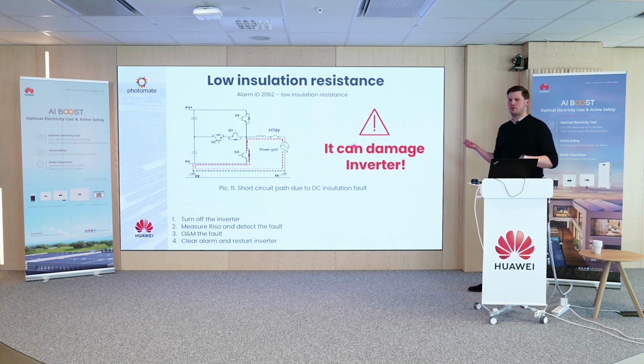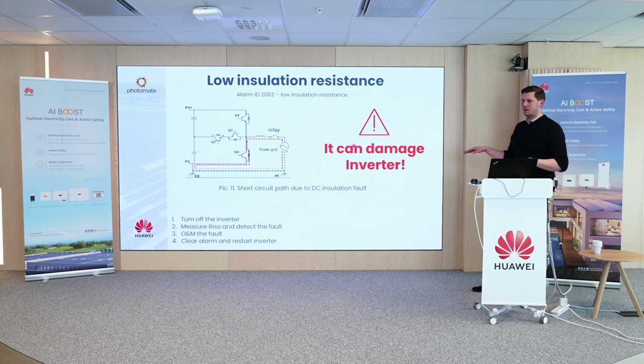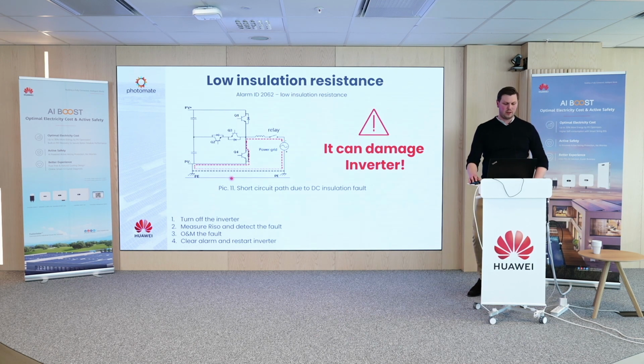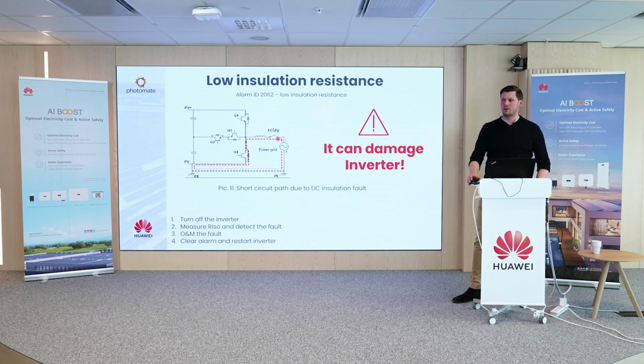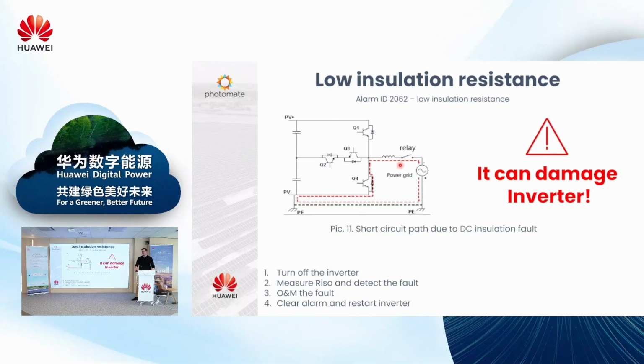But if you have a problem with an alarm like this, you should turn off the inverter before you go on site, or ask the owner to do it for you. Because the inverter, which will be trying to check this insulation resistance, will have a short circuit path here, and it will damage the relay at the output during a few attempts. We had some cases where the warranty was voided because of this problem: the insulation resistance alarm was active for several days, and after that it just destroyed the equipment. So your job is to turn off the inverter first and only then go on site and detect the problem. Otherwise, you might damage your equipment.